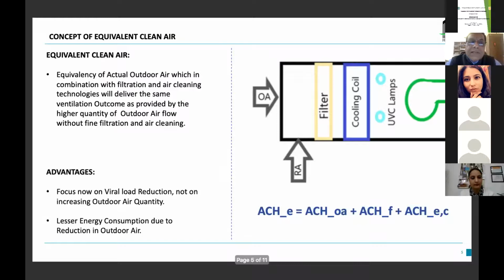That equivalent you can find out from the ACH of outdoor air, the actual air which you are supplying, plus the actual air equivalent of the filter and the actual air equivalent of the air cleaning technology, based on efficiency. The advantage of this approach is that the focus now shifts to viral load reduction, not on increasing outdoor air quantity, and how we reduce it will depend much on the air cleaning technology you adopt. And this will provide lesser energy consumption due to reduction in outdoor air.